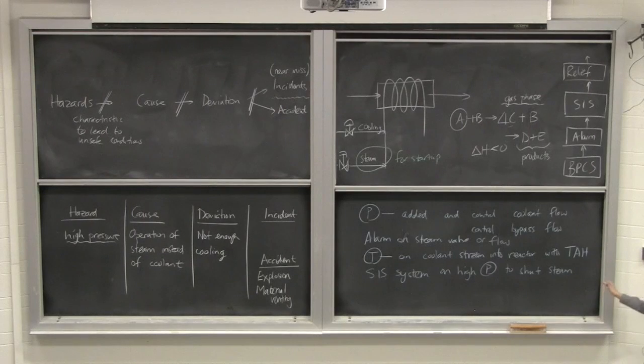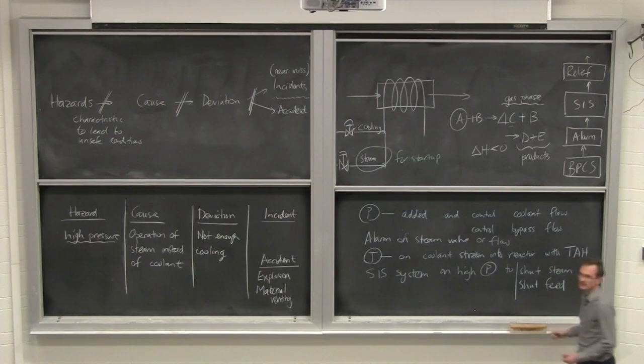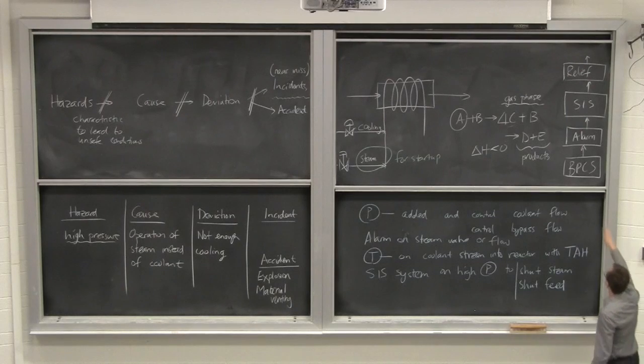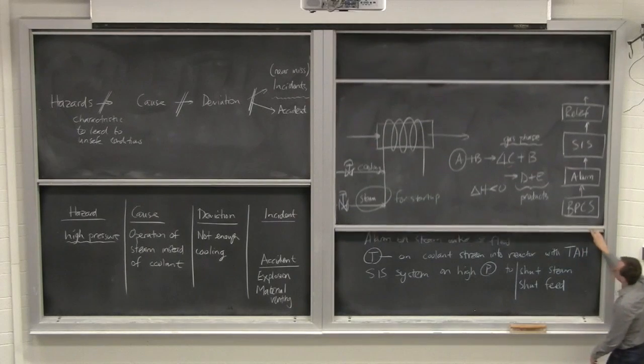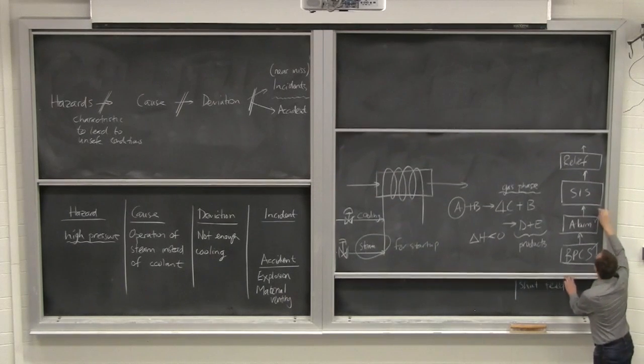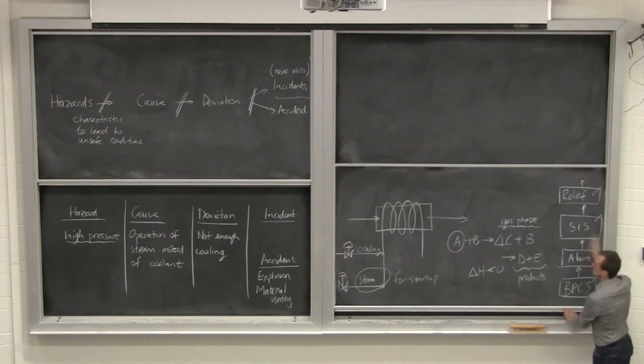So SIS system on high pressure to shut steam, okay? And you probably want to consider that SIS not only shutting steam, but also shutting feed, to shut steam and to shut feed. Okay, so we could go, and this is what we should be doing, going down, every one of those suggestions actually triggered one of these. We could go address this problem with the basic process control system, with alarms, or with SIS, and we could have even put on relief.